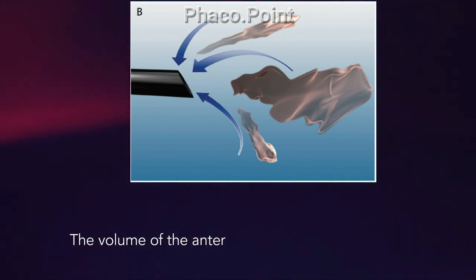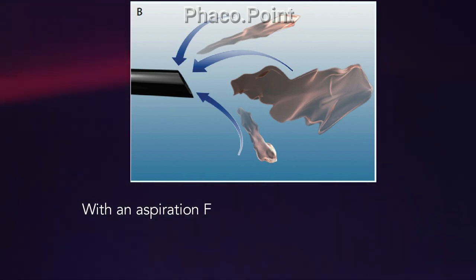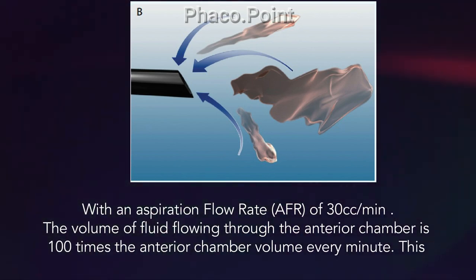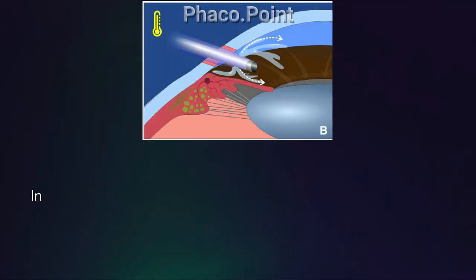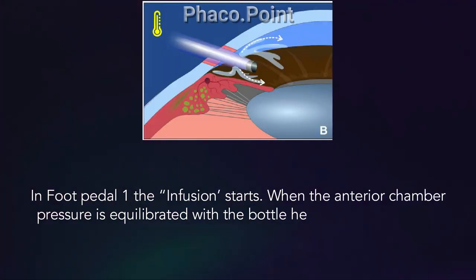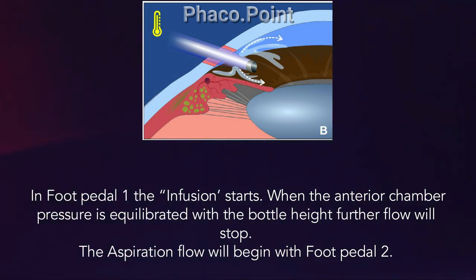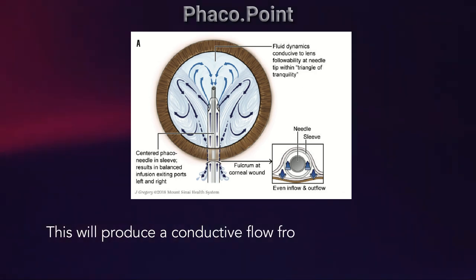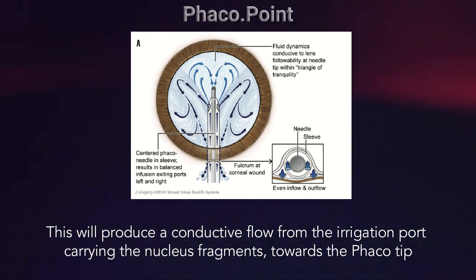Consider that the volume of the anterior chamber is just 0.3 ml of fluid. When an aspiration flow rate of 30 cc per minute is set, the volume of fluid flowing through the anterior chamber is 100 times the anterior chamber volume every minute — quite a lot of flow. In foot pedal 1, the infusion starts. When the anterior chamber pressure is equilibrated with the bottle height, further flow will stop. The aspiration flow begins only with foot pedal 2. This produces a significant convective flow issuing from the irrigating port of the silicone sleeve, carrying the nuclear fragments towards the phaco tip.